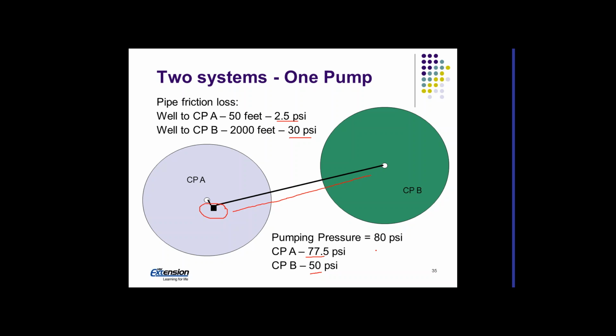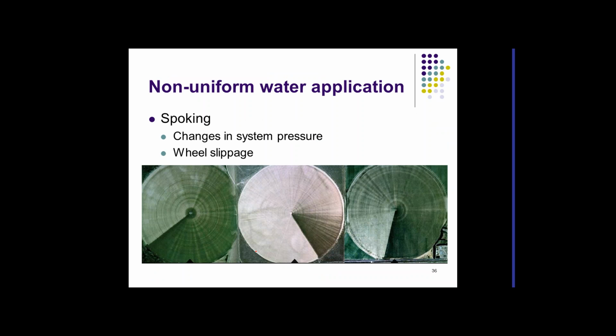If I have a variable speed drive, I can force them both to operate at 50 psi so that I gain medium pressure on both systems. Or I could make one run at low pressure and one at high pressure, depending on maybe the crop that's being used. Here's an example of spoking.